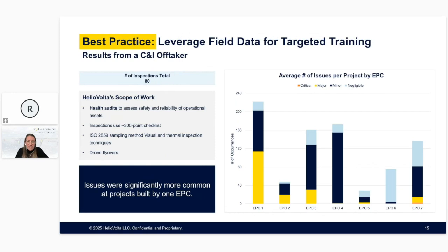As you can see here, there was one EPC that they worked with that had a much higher number of average issues per project than the others. We also saw issues at projects built by this EPC that simply weren't found at other sites: the wrong equipment was installed that wasn't specified in the drawings, there was consistently poor wire management, and there were systemic cross-mated connector problems.